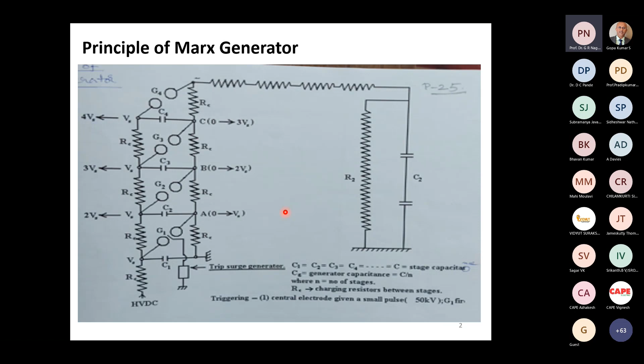Current generator, equivalent circuit. Oh, sorry. I must say one thing more here. I said triggering of this. How do we do that? This is the first stage sphere gap. You'll see that this one sphere at the high voltage end has another sphere. What we do is this sphere has got a needle at the center, isolated from the spherical body. When we want to trigger the generator, we apply a pulse to this needle that causes a spark between the needle and the sphere. This ionization causes spark over of this main gap.